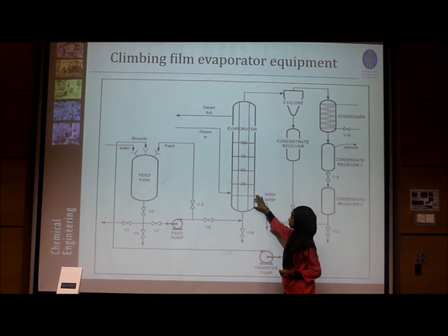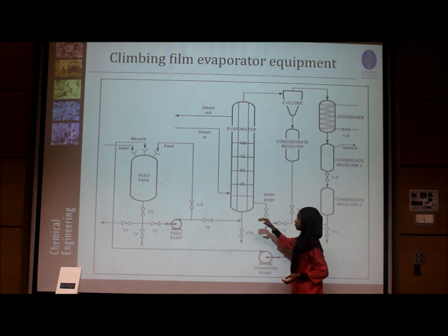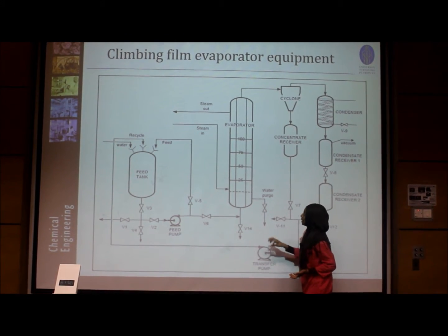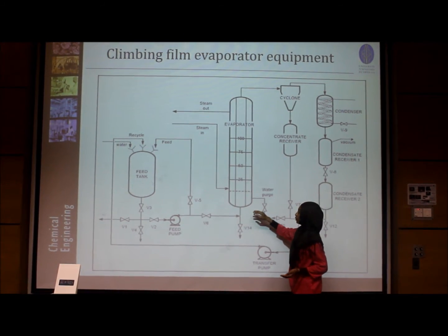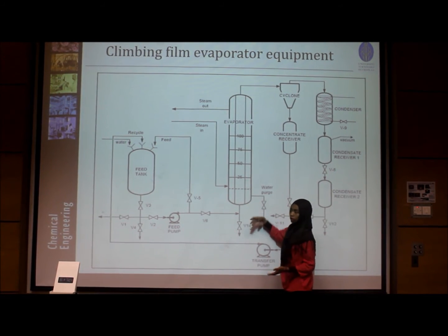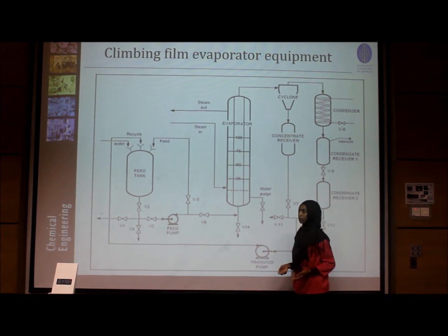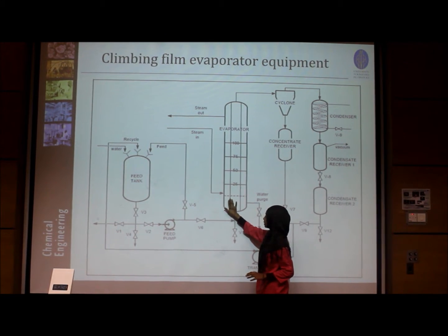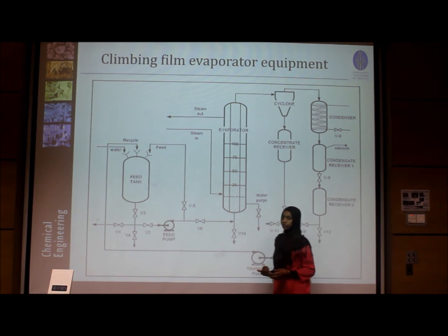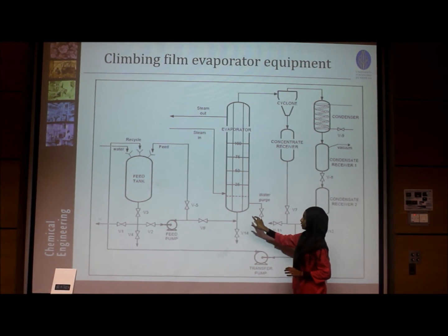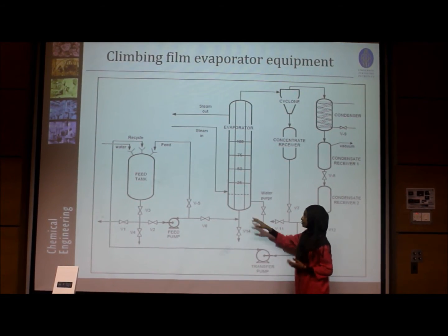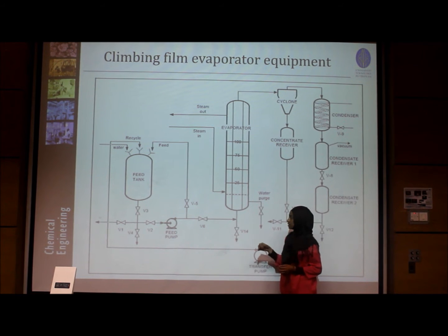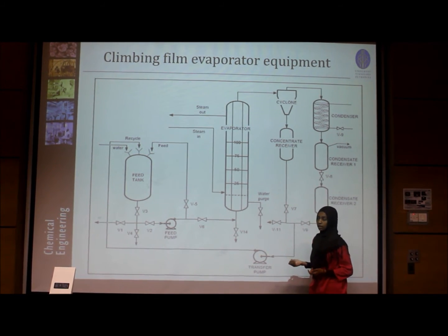At the lower section, the liquid will be heated up until its boiling point and then will start to rise because vapor is produced. The liquid and vapor go upwards, vapor production continues, and the product starts to form a film on the inner side of the tube of the evaporator. This co-current flow between the liquid and vapor produces turbulence in the liquid flow, increasing the velocity and heat transfer rate of the mixture.